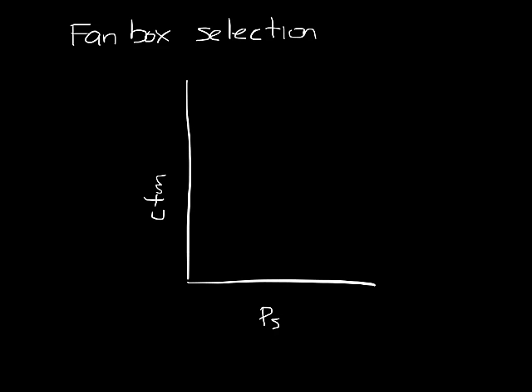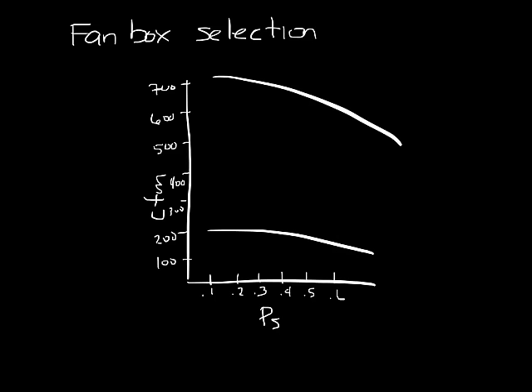Now in real life fan boxes don't operate just on the minimum or maximum fan curves. So how do you use the fan curve for fan box selection? Let's draw a fan curve real quick. What you usually know when selecting a fan box is what pressure it'll operate against and how much airflow you need. So any point within the two fan curves is an acceptable selection for the unit.